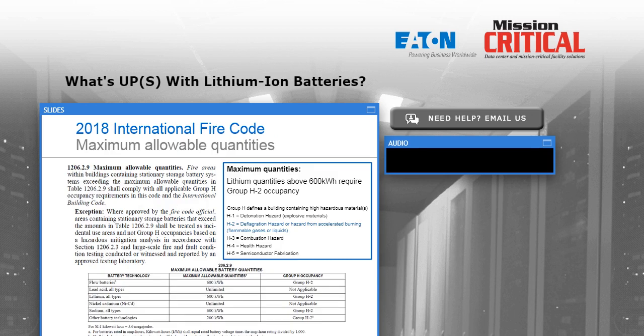This next slide is titled Maximum Allowable Quantities, and this is the quantity at which I need to switch my room to a more fire-resistant room with fire-rated doors and windows, and also fire suppression systems get more complicated at that point. However, if you look in the fine print in the table, it says lithium, all types - the maximum allowable quantity is 600 kilowatt hours.